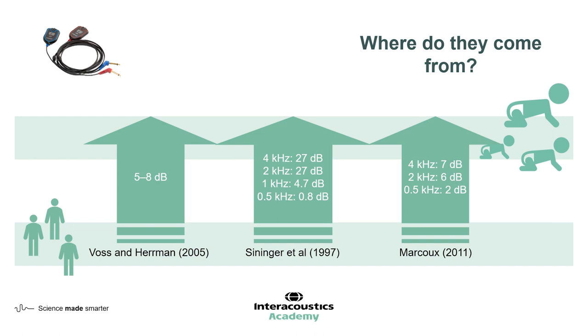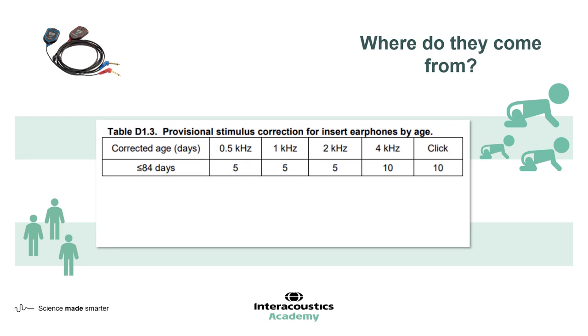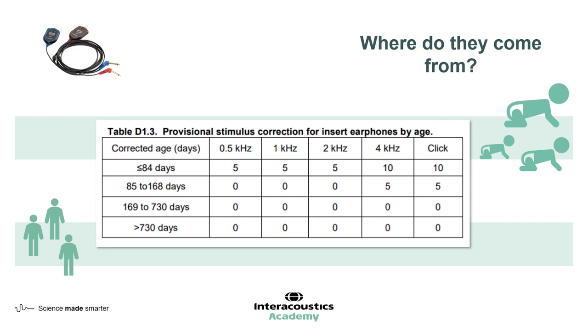Correction factors were decided upon based on these studies. The mean of the three studies at 4 kHz was 14 dB. However, the Syninger study differed quite considerably from the other two, so the other two were given greater weight, resulting in the choice of 10 dB. These are the correction factors for inserts for under 12 weeks of age. A fixed value is used for this age band, as the literature data showed too much inter-subject variability to deduce a trend within this band. Over 12 weeks, correction factors are likely to reduce with age, so there was a decision to approximate a gradual reduction in two steps — firstly at 12 weeks and secondly at 24 weeks. There are no correction factors over the age of two years for insert earphones.